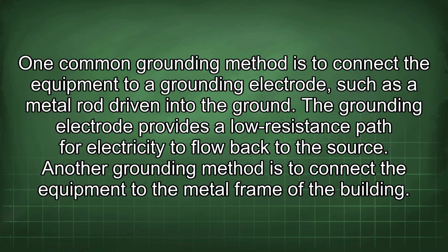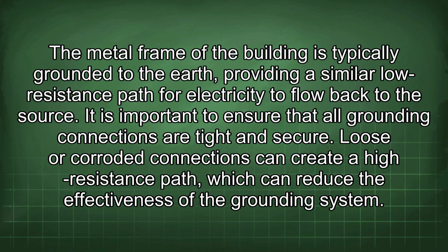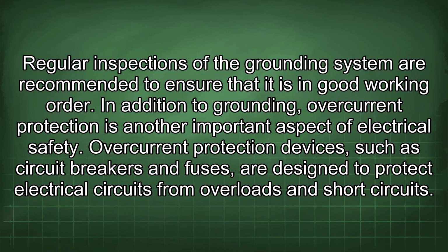Another grounding method is to connect the equipment to the metal frame of the building. The metal frame of the building is typically grounded to the earth, providing a similar low resistance path for electricity to flow back to the source. It is important to ensure that all grounding connections are tight and secure. Loose or corroded connections can create a high resistance path, which can reduce the effectiveness of the grounding system. Regular inspections of the grounding system are recommended to ensure that it is in good working order.